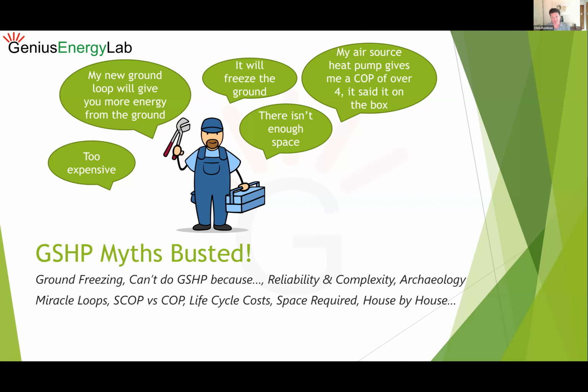I mentioned seasonal COP and COP. COP is a spot coefficient of performance. The rating point for air source heat pumps is 7/35 - that's 7-degree air temperature, 35-degree load temperature. The rating point for ground source is 0/35. Now remember, I talked about the lift that's being carried out by the heat pump.